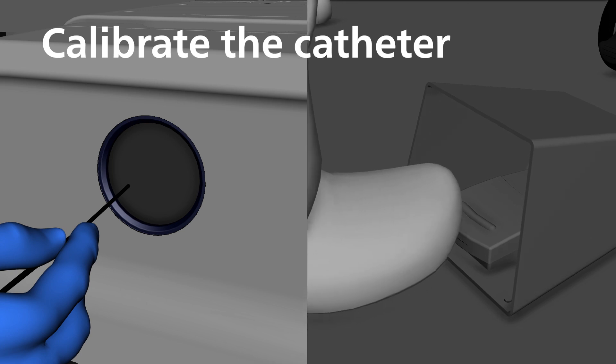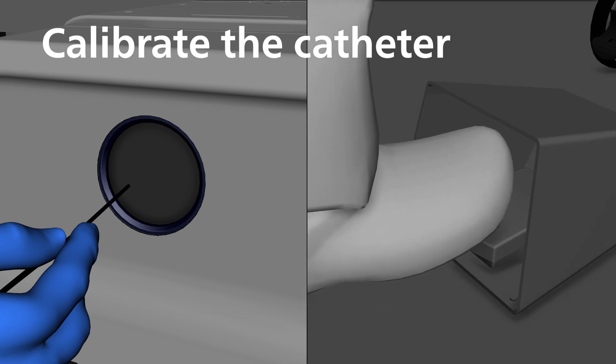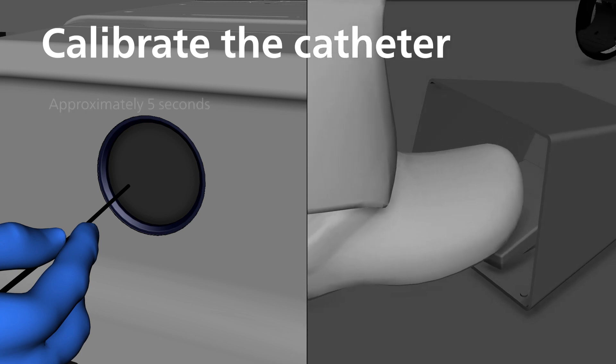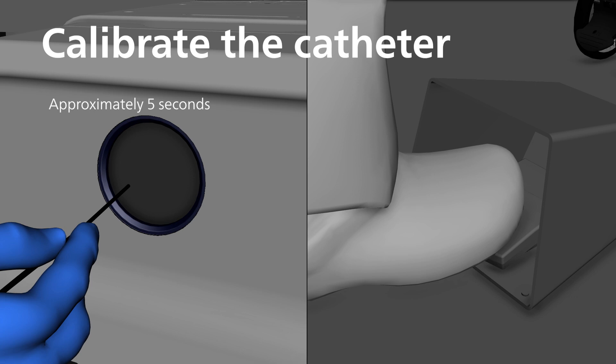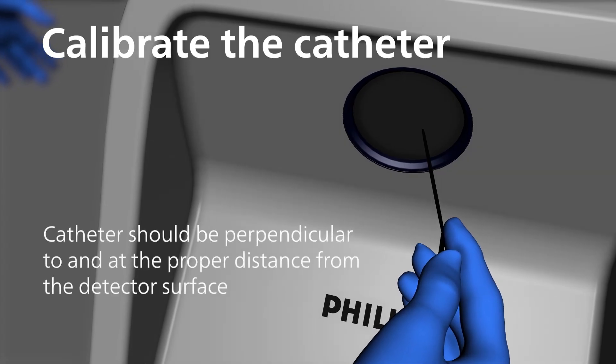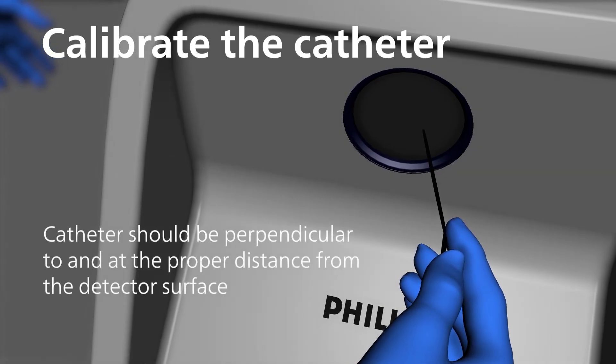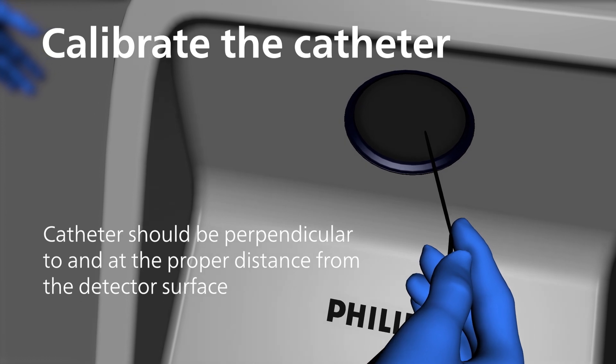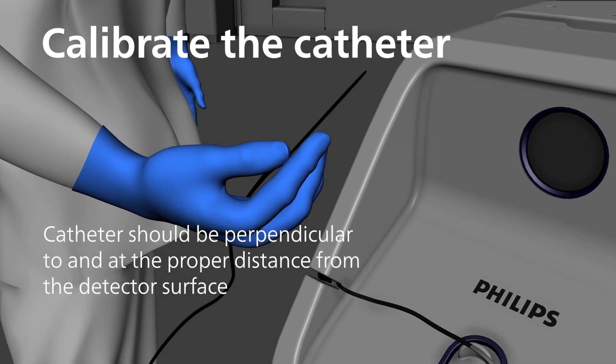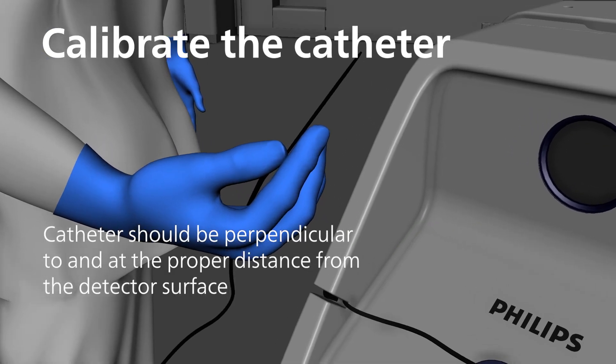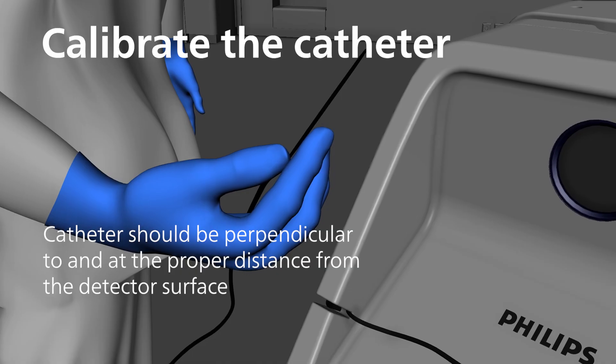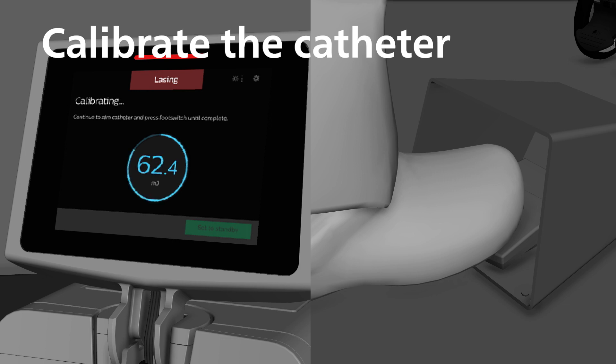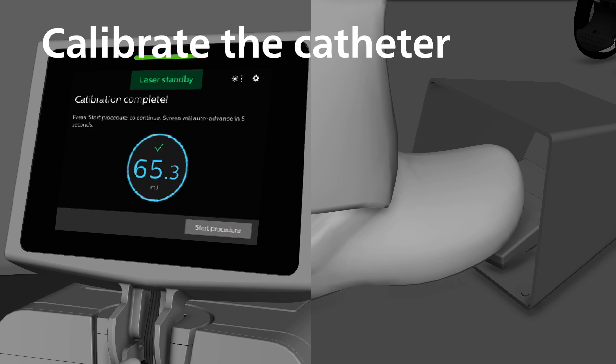Depress the foot switch until calibration is complete. This will take approximately 5 seconds. The system may not pass calibration if the catheter is not perpendicular to and at the proper distance from the detector surface during calibration. While calibrating, the system will display its progress. The circular progress bar will fill as calibration progresses. Energy readings will be displayed during the process.